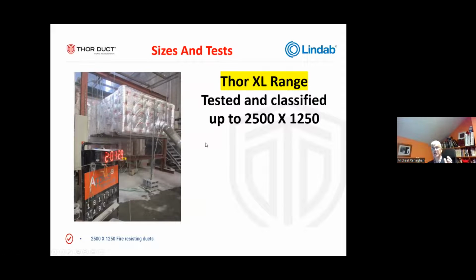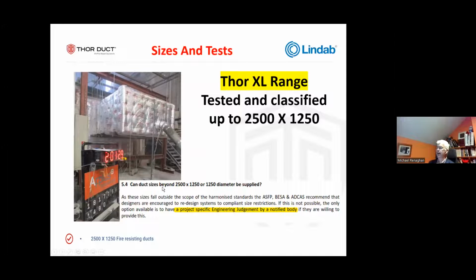The issue we have at sizes comes down to one thing primarily. We've got dual systems in the UK and Ireland, where we design the smoke and we design the fire as a dual system, regular ventilation and fire. In the continent of Europe, they don't do that. They have the smoke system stand alone. So that's just something to be aware of. That's why we have the size issues. Okay, so again, you can do it bigger, but you need a project-specific engineering judgment by a notified body. Good luck with getting one of those.